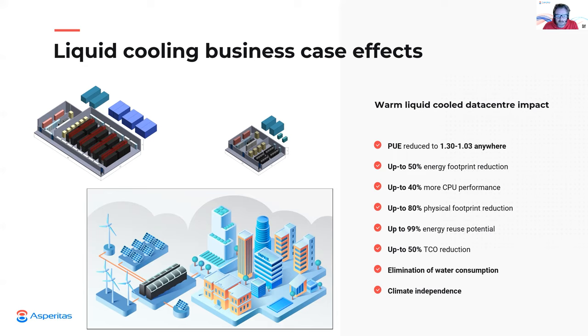If, for example, an edge facility is integrated in urban environments with immersion cooling, an ERF can be achieved at 99% due to the integration into localized and even industrial heat demand. All of these factors can add up to a potential of 50% TCO reductions. A cherry on the pie, which should not be ignored, is that elevated temperature operation allows the elimination of evaporative cooling, thus addressing the water consumption challenges. This will stimulate further political support in scaling out data center strategy towards sustainability.